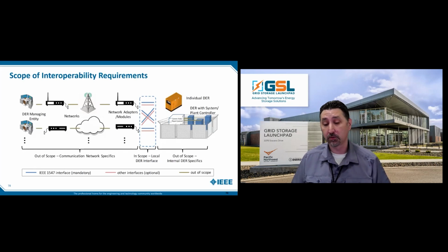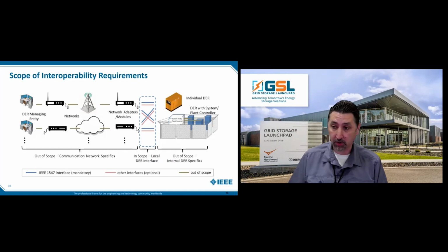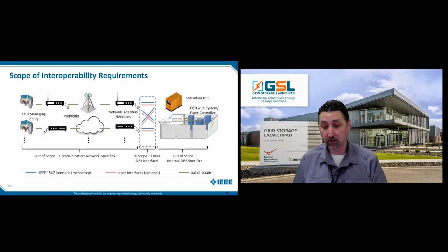And why that's important is because if you think about a DER system, you could have Sunspec Modbus operating locally, but it might not be just the 1547 requirements. It could be beyond that, or a subset of those. It could be proprietary stuff going on within the system. So if you've built an inverter, you have your own secret sauce within that inverter. That's not in scope, but that interface needs to support all of the 1547 interactions.